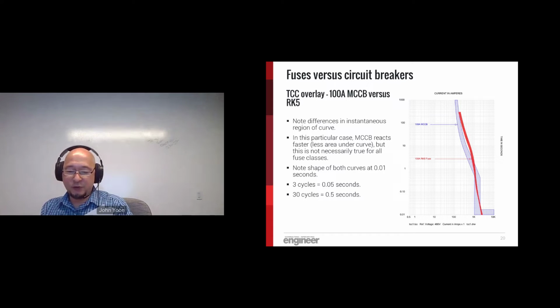You can see that the characteristic transition between the magnetic function and the thermal function in the blue band is at about half a second or 30 cycles. We can also see that in this particular case, the circuit breaker reacts considerably faster in the overload region of the graph at the top. However, when we take a look further down in the short time region of the graph where the magnetic function of the breaker operates, there's pretty high uncertainty regarding where the circuit breaker will clear a fault in comparison to a fuse. If we go down to the bottom of the graph again, see that dog leg that's characteristic of a thermomagnetic breaker. The top of that dog leg is at 1 cycle, 0.0167 seconds. The circuit breaker can trip anywhere within that shaded blue region, whereas the red band representing the average melt time for the fuse is really well defined in this region. So down there, I can't tell you if the fuse or circuit breaker is going to clear first.